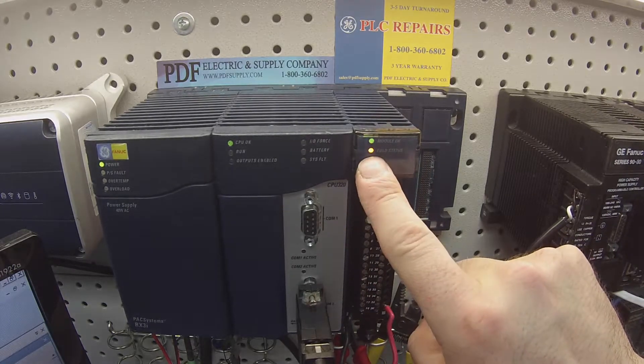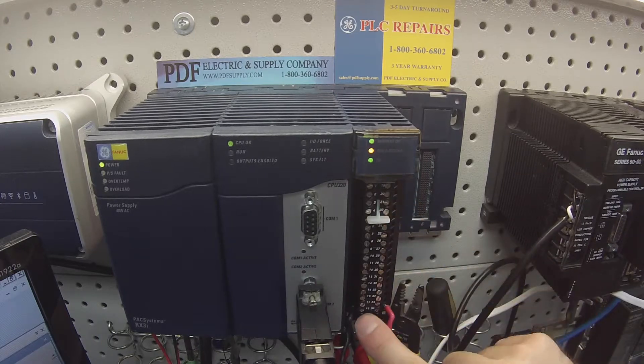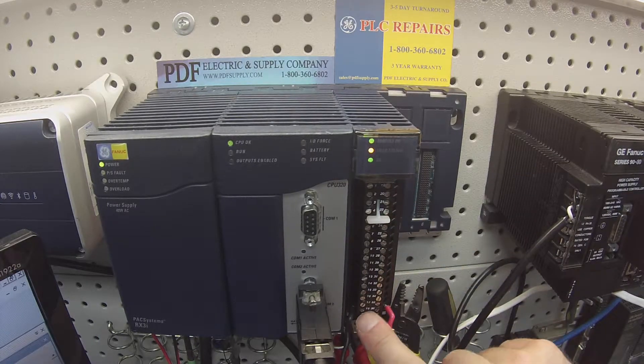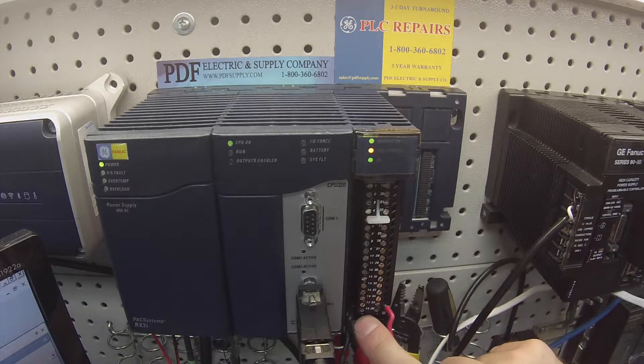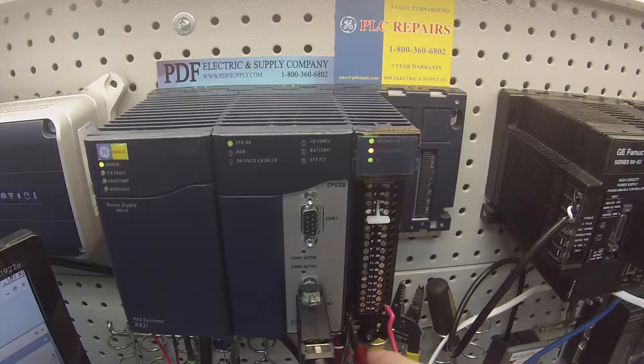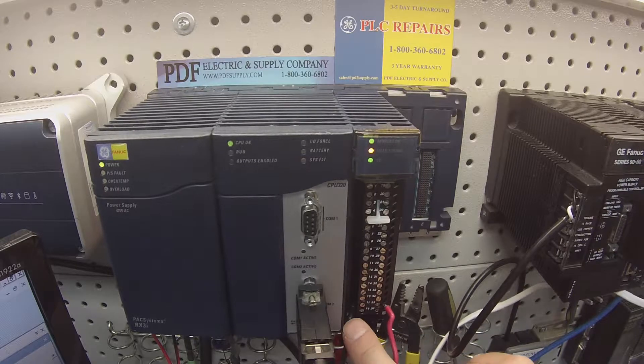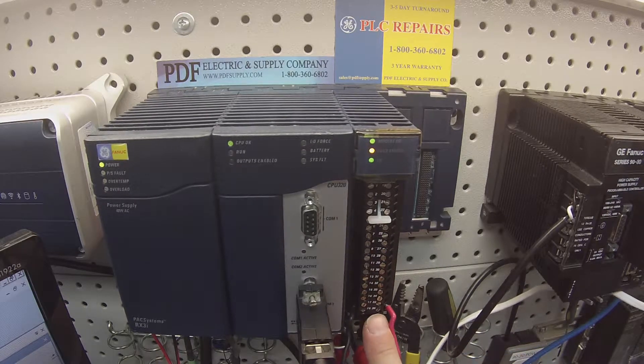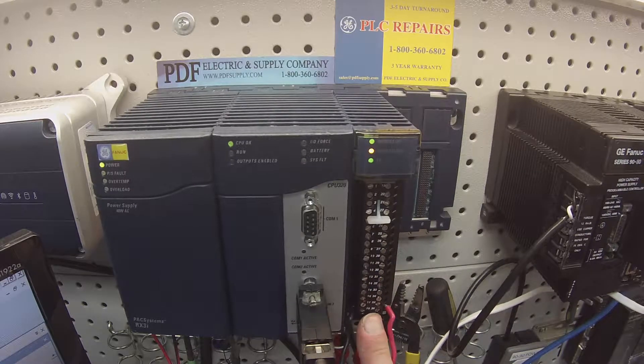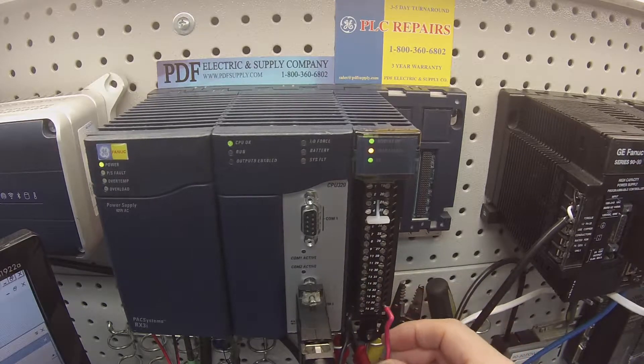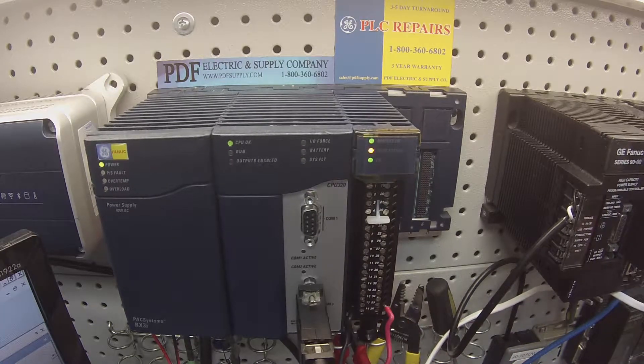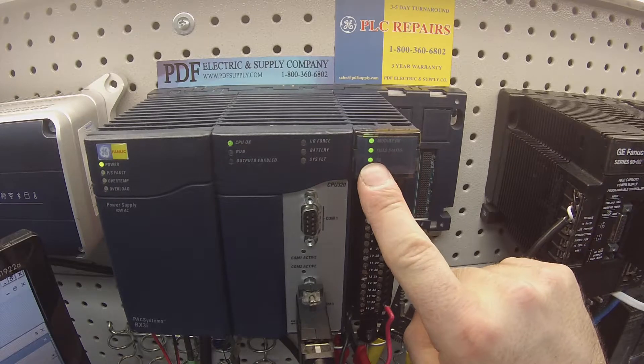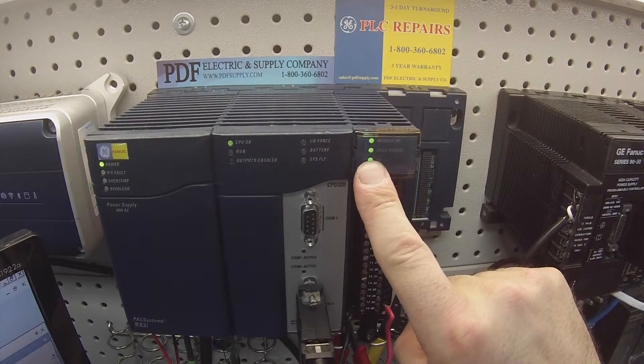Now my field status is orange telling me that it detects the terminal block but it doesn't detect the power it needs to power up the module and give us output values. On screw number 18, bottom left hand corner, I've got my negative lead from a 24 volt DC power supply and my terminal number 36, bottom right terminal, has the positive lead from my 24 volt DC power supply. So I'm going to power that up and you'll note that my field status has changed to green.